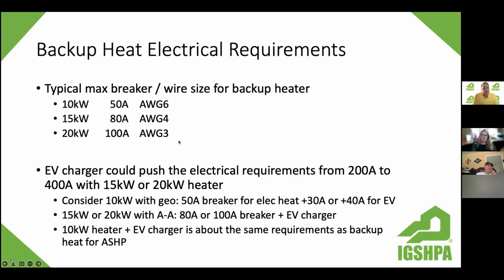Copper is really expensive right now. I just did some wiring, and it has certainly gone up significantly. But in this case, we might be in trouble with our electrical service with this 100 amp breaker, depending upon what else is on the service. As we start to look at electric vehicle charging requirements, that's a load that could happen any time of day, so we have to plan for that breaker. In a lot of cases, EV chargers are 30 amps, 40 amps, some are 50 amps.